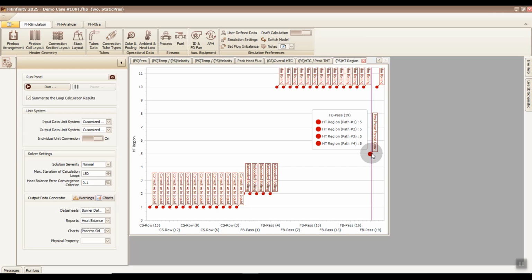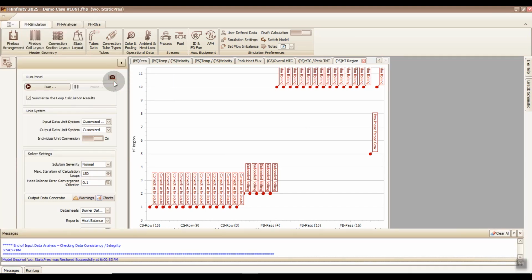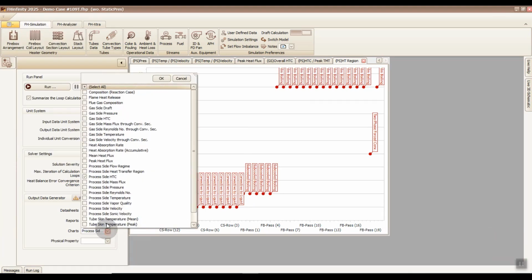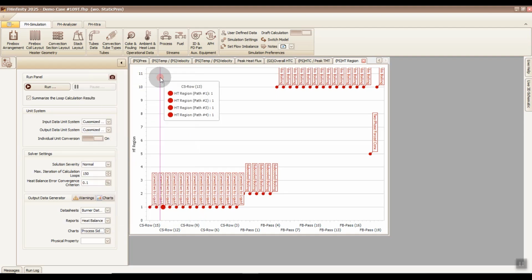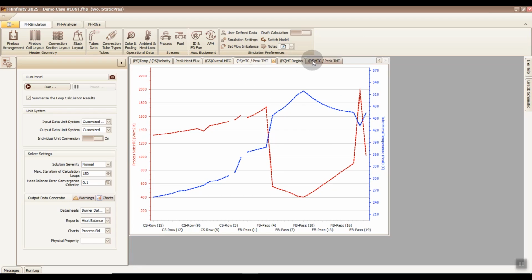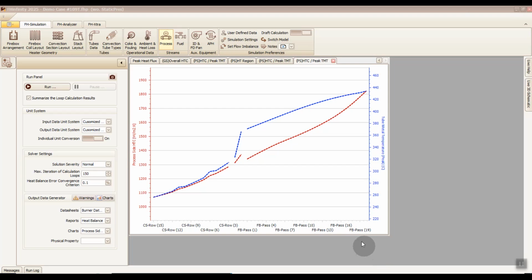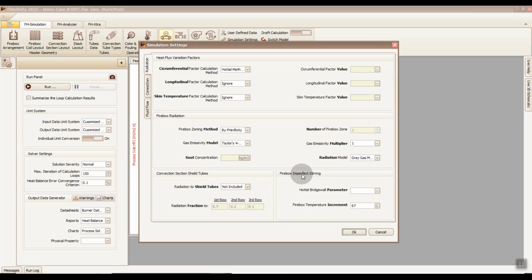Finally, in the second-to-last tube, the flow enters a two-phase forced convection region, which explains the secondary peaks in both curves. If we compare this result to our earlier model using the API 560 method, the difference is clear. The proprietary FHinfinity approach captures the nuanced physics of the process far more accurately, bringing the simulation much closer to actual field behavior.